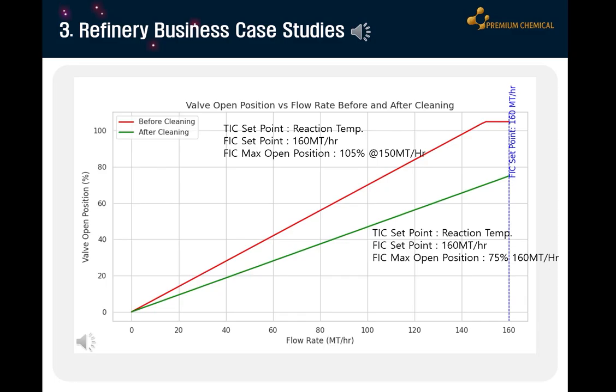Before cleaning, the valve had to be opened to 105% to achieve the desired flow rate, but after cleaning, the valve was opened to only 75% to achieve the same or higher flow rate. This suggests that the cleaning effect cleaned the flow path and improved the flow efficiency.